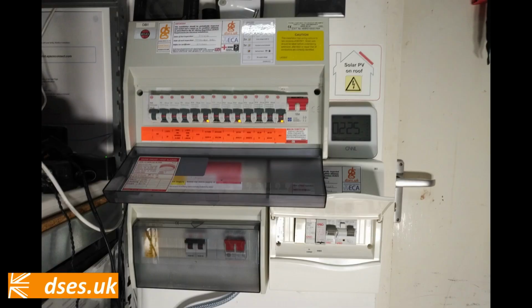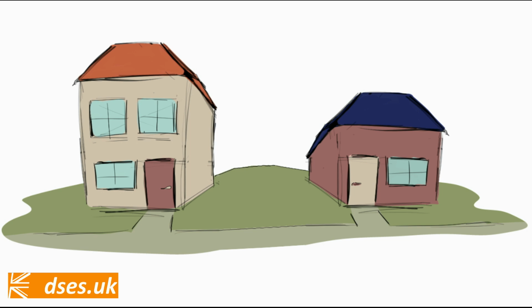With regard to my Garo unit, that already has a 40 amp, 30 milliamp Type A RCBO installed for my shower and EV charger, so having another device of the same rating in line isn't best practice and doesn't comply with what BS 7671 says about selectivity. But that's not really a problem here, as the two devices are right next to each other. That sort of thing is more of a ball ache where you have, say, power to an exterior building with a 30 milliamp RCD inside the house and another at the outbuilding itself.